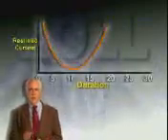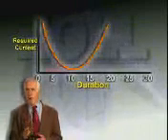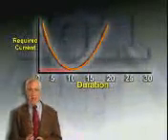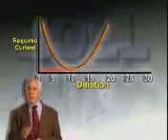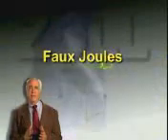There's another downside to increasing duration. Several studies demonstrate there's an optimal time for the duration of a defibrillation shock. Data confirm that a waveform longer than about 12 milliseconds requires more energy to achieve the same efficacy. So adding joules by extending the time doesn't always increase shock efficacy. Go beyond the optimal duration, and you're looking at faux joules — they look good, but they don't have real value.